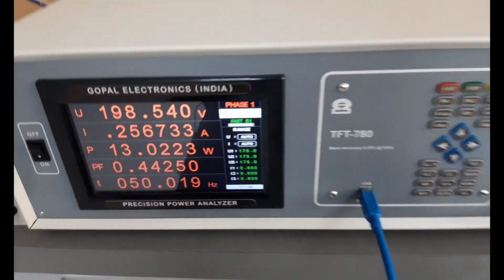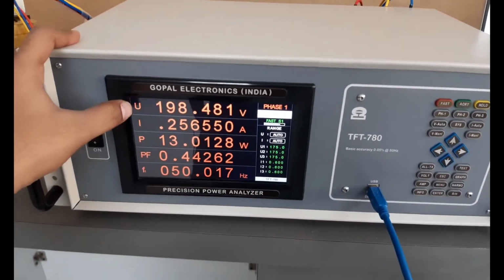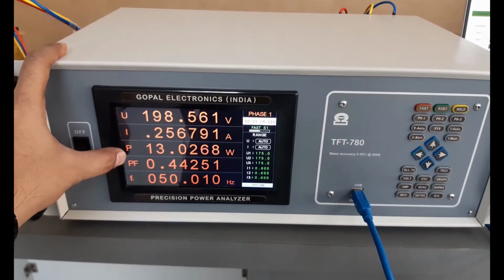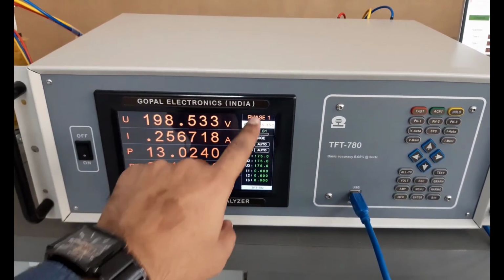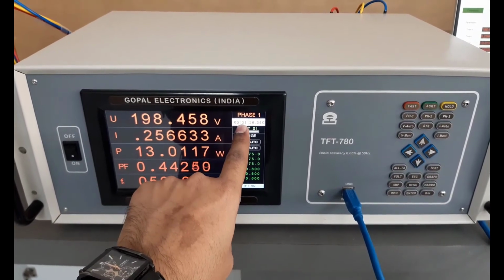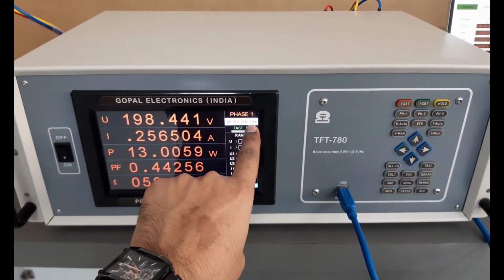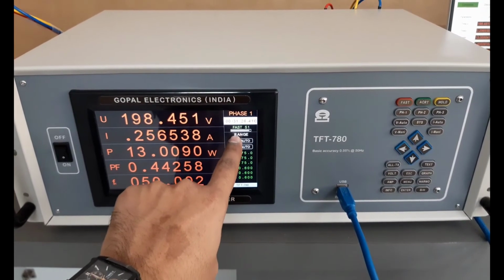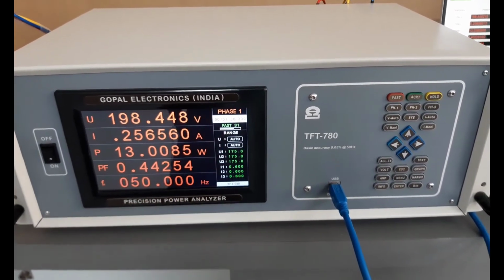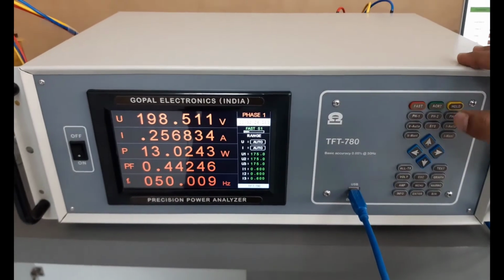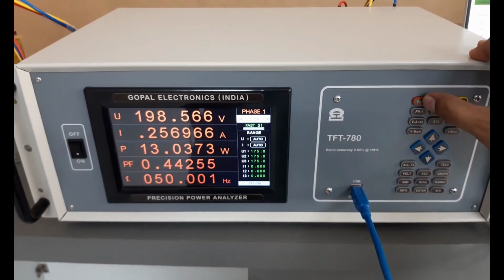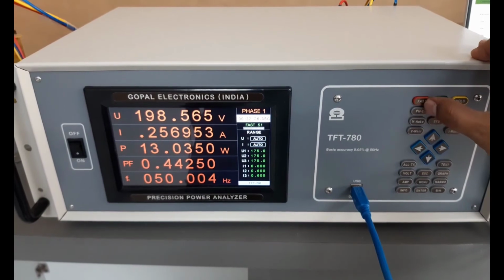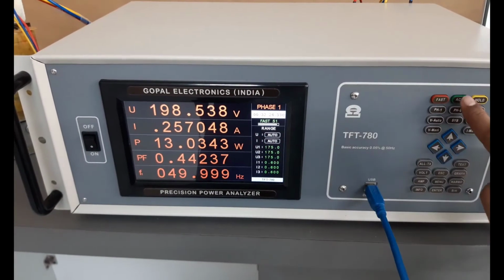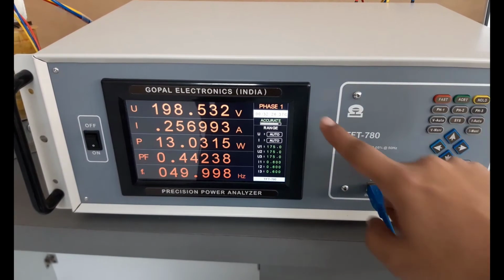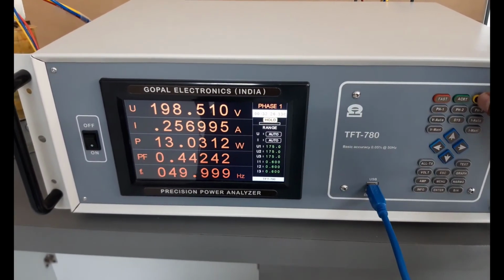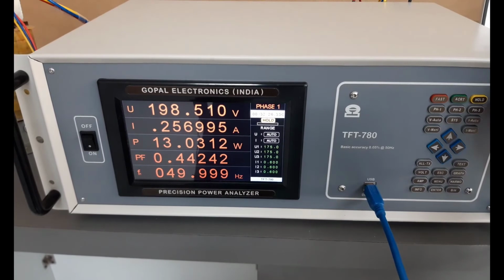So let's check the functionality of the equipment. This is displaying voltage, current, power factor and frequency of phase 1. This is displaying total running time, instrument internal temperature, measurement speed, and this is range table for voltage and current. This is the key for measurement speed. If I press fast, the display update rate will be fast. Accurate mode for fine measurement, hold to hold the measurement and take the readings.